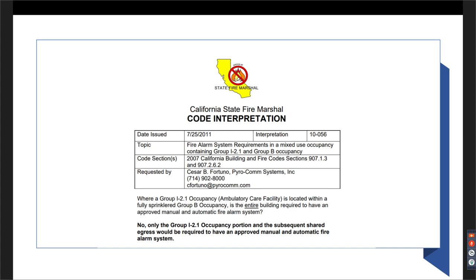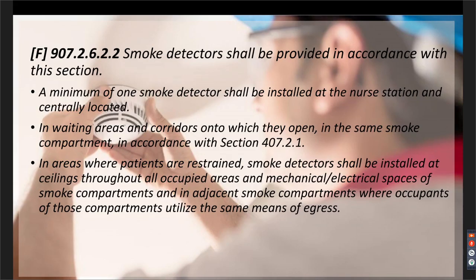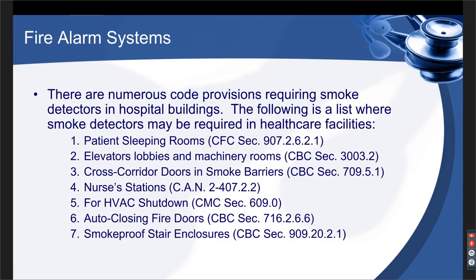When smoke detectors are required, interestingly, there are not a lot of requirements for smoke detection in 907. 907 basically lists these areas. It says you have to have a minimum of 1 smoke detector at a nurse station, centrally located. You have to have smoke detectors in waiting areas and corridors to which the waiting areas are open within the same compartment, assuming the waiting area is open to the corridor. And then if you have, for instance, a psych clinic or a mental health clinic where patients are restrained, then smoke detectors need to be installed throughout all occupied areas, as well as mechanical and electrical spaces, to detect fire earlier, so that we can take an immediate action and get the restrained folks out. Those are the only three required by 907.